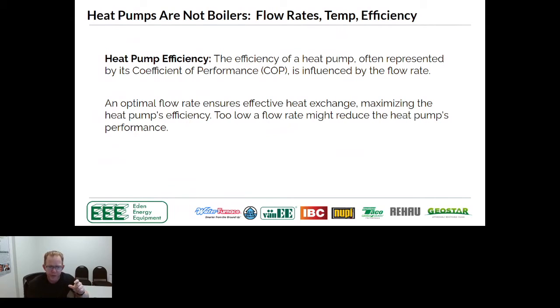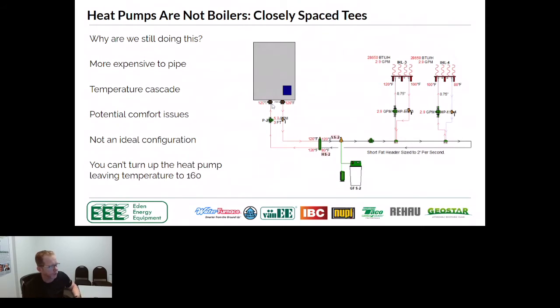So the idea is we want to make sure with a heat pump that we always have optimal flow rates. We want to make sure we have very, very good heat exchange through the unit. And we want to recognize what will happen if we don't have enough flow going through that heat pump and what the end results can be. The other thing that we want to talk about is some of the piping aspects of how we pipe these units. So here, what I've done is I've got a boiler that's tied in on closely spaced tees, as you can see. This would be the older school way of doing things.